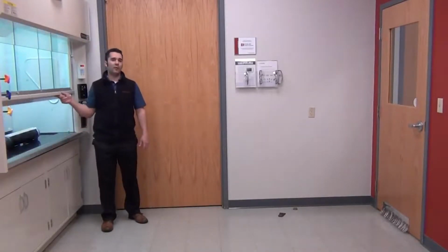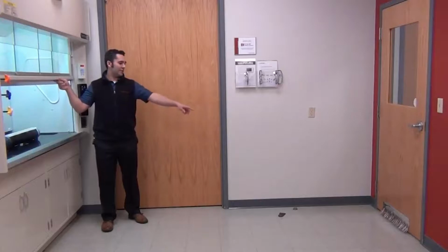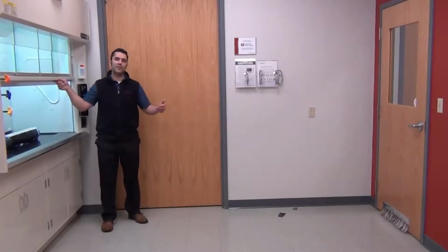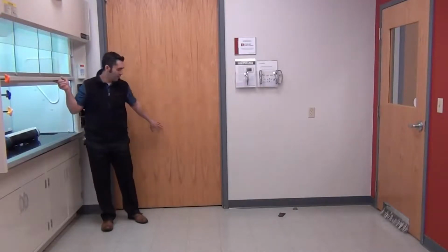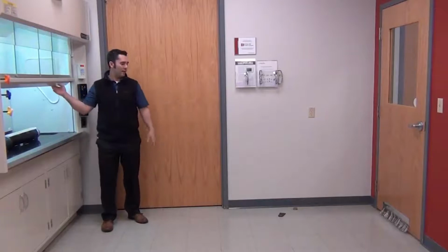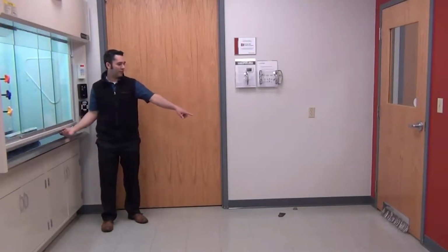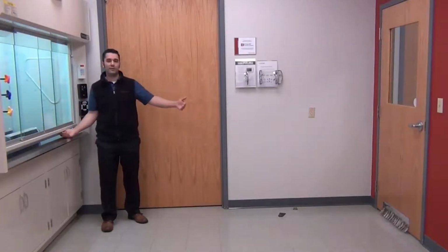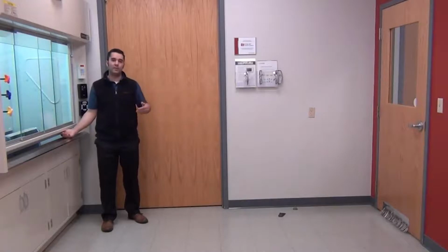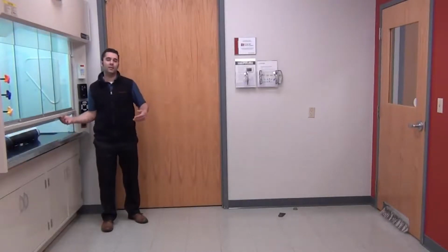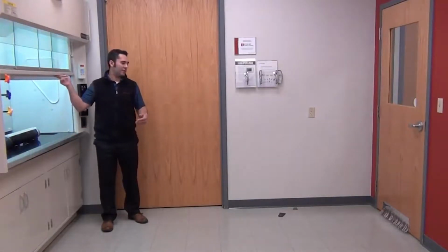And as I open and close my fume hood sash, you can see that my pressurization is always going to stay net negative. And in this particular space, I think we have the offset set at about 300 CFM negative because I have two doors in here. But as you can see, my hula skirt on the door is going to remain relatively constant, but it's always going to be flowing into the room, guaranteeing that I have negative pressurization in here.